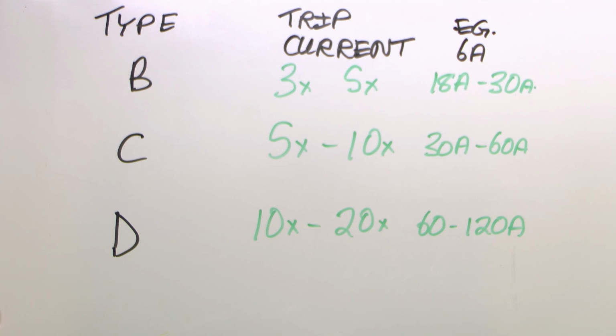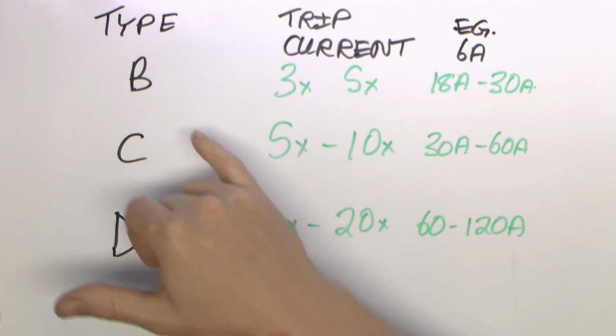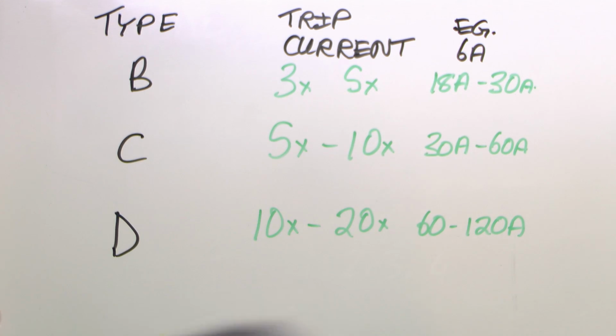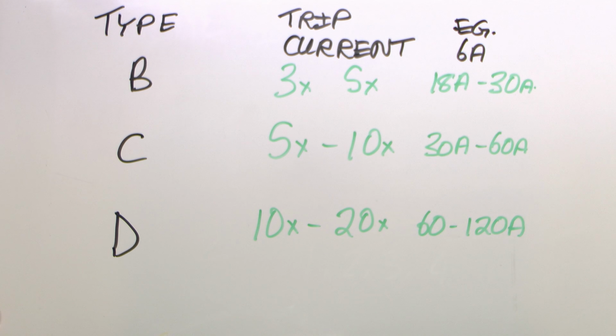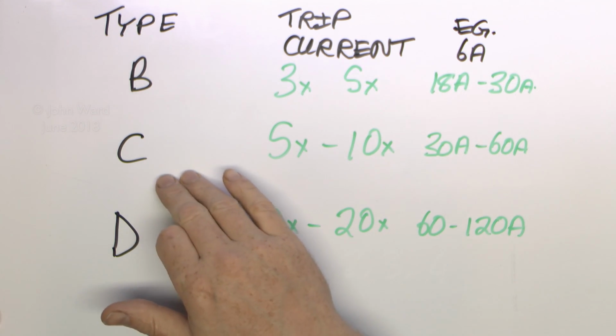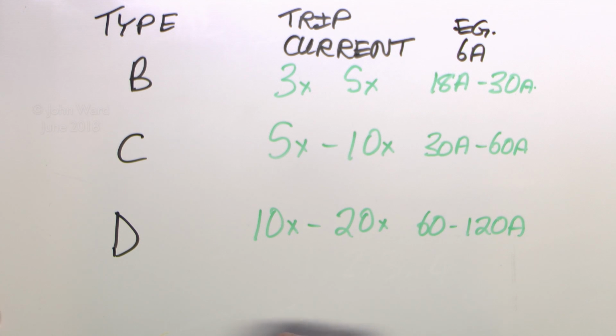Now the main reason for having these different ratings is that most pieces of equipment will have various types of switch-on surges or starting currents. So for normal applications, say in your house, Type B would be the most common because most of the stuff in your house doesn't have a particularly large surge when you switch it on. Things like incandescent lamps do have a bit, but they're pretty much gone anyway, and certainly other equipment is not normally going to be much of a problem. But it may be necessary to use Type Cs and even Type D in some cases, because certain types of equipment do have a much larger surge when you turn them on. Electric motors would be a fairly common example of that, and it's often the case you may need to use Type Cs for electric motors, simply because when you turn on a motor, the initial current to start it is significantly greater than the current it would run at.